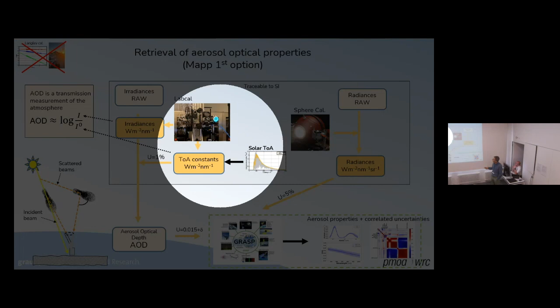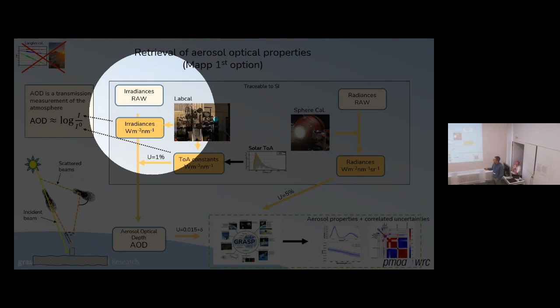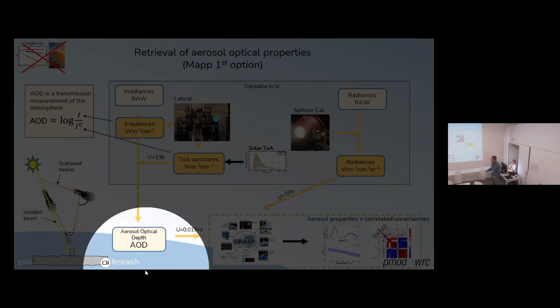So instead of going to a high mountain station, we go into the lab, we go in our basement, we do the calibration there. And so the irradiances that this instrument measures are now in SI units, watt per square meter per nanometer if you have a spectroradiometer. What we need is the top of the atmosphere, which nowadays you can get from satellites. Our approach was to use a solar spectrum that you can get from the literature, from satellite-based measurements. So they are completely independent. The instrument and the solar spectrum are completely independent. You bring these things together, and then you can also calculate the aerosol optical depth. So we did that.